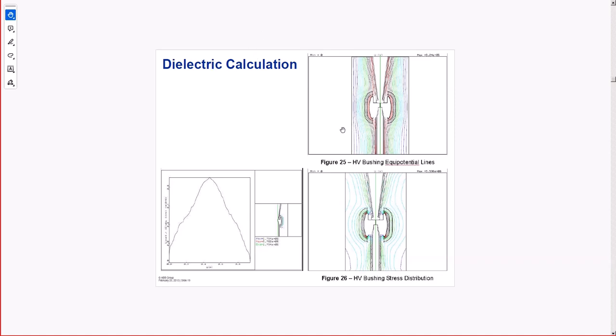The manufacturer will do all these calculations for bushing, equipotential. The bushings are stressed in electric field, not magnetic, like we saw the leakage inductance there, in the tank, this is electric field. The electric field is just going to flow through the bushings this way because it is actually connected to the power cables, but from there to the actual three-phase in the tank. But in the middle is passing the tank. The tank is grounded, so the actual voltage electric field is zero. So that's why you have stress on the bushing all the time. So the bushings are a weak link, as you saw. That is the third factor, after the short circuit of windings and the winding collapse. The third was the actual bushing failure.